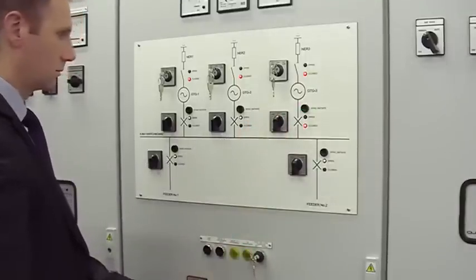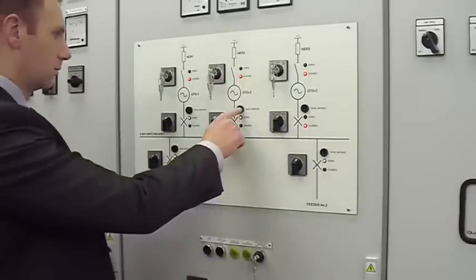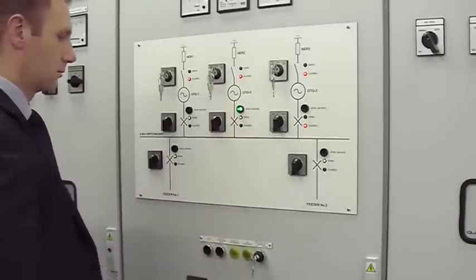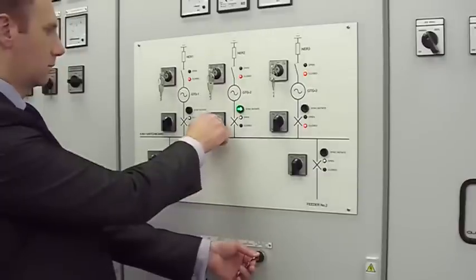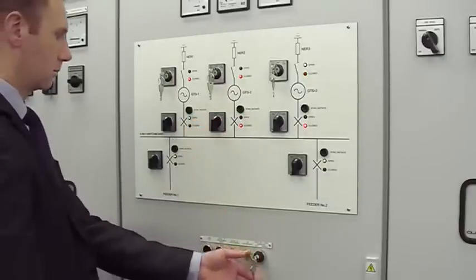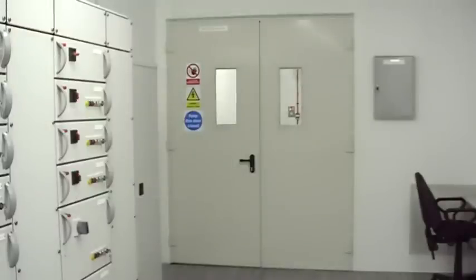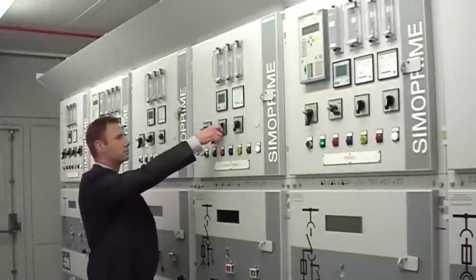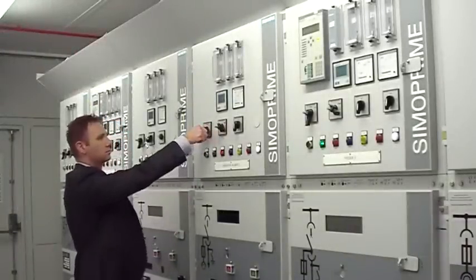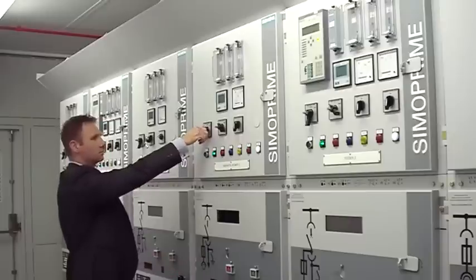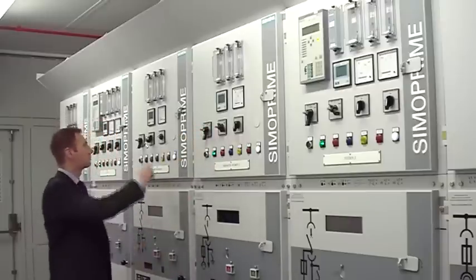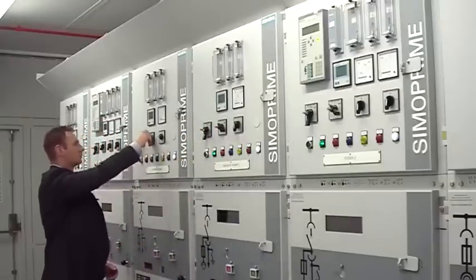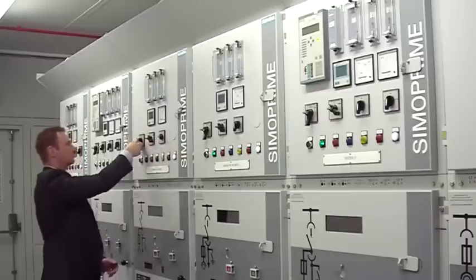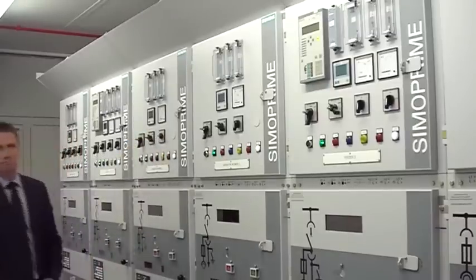A simple traffolite mimic display shows the layout of the medium voltage system and gives the operator control of the MV circuit breakers. A separate medium voltage room houses the 6.6 kV switchgear. This room is lockable and permit controlled to prevent unauthorised access from day-to-day operators. The switchgear consists of 3 generator incoming vacuum circuit breakers and 2 feeder circuit breakers for connection to the customer's power system. A local remote switch allows the operator to open and close the circuit breakers locally from the switchgear.